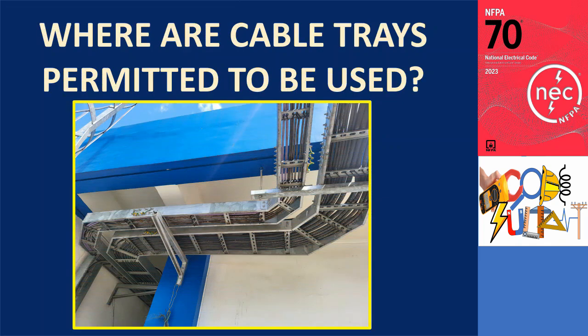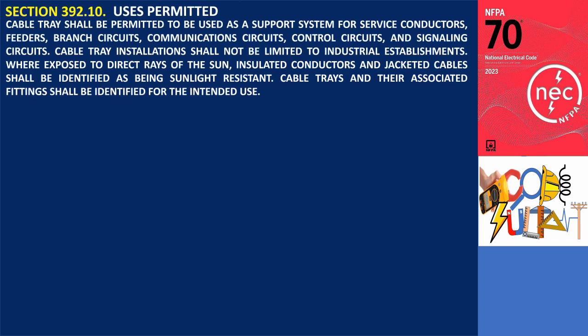Where are cable trays permitted to be used? Section 392.10 states that cable trays shall be permitted to be used as a support system for service conductors, feeders, branch circuits, communication circuits, control circuits, and signaling circuits. Cable tray installations shall not be limited to industrial establishments. Where exposed to direct rays of the sun, insulated conductors and jacketed cables shall be identified as being sunlight resistant. Cable trays and their associated fittings shall be identified for the intended use.